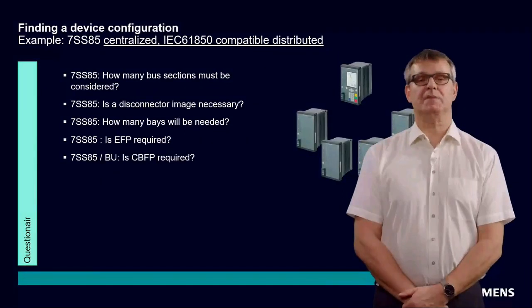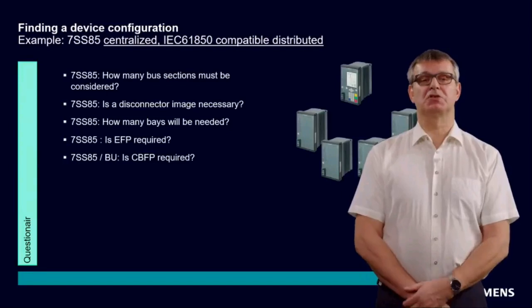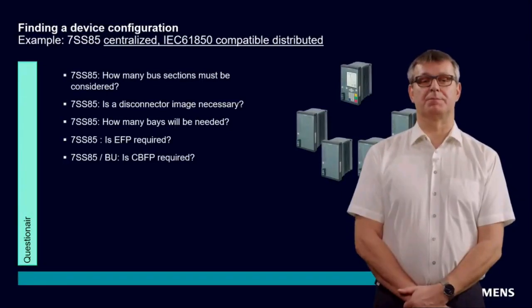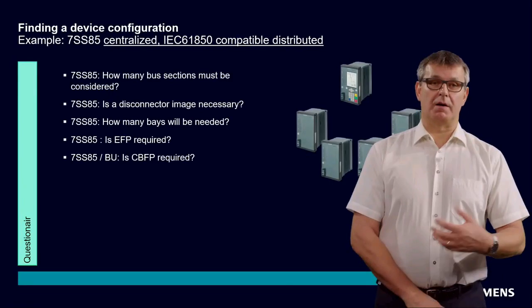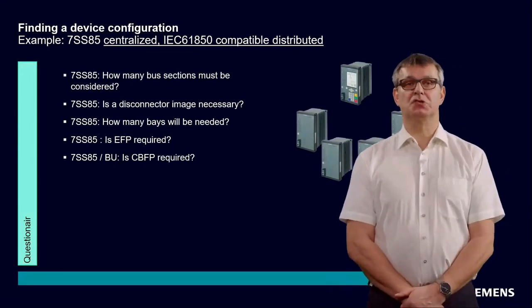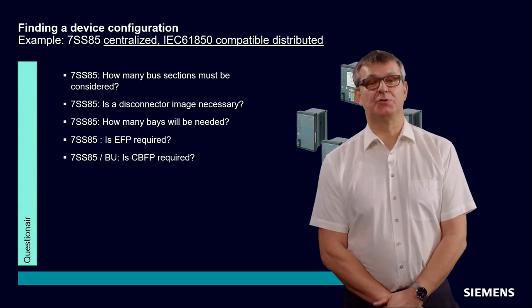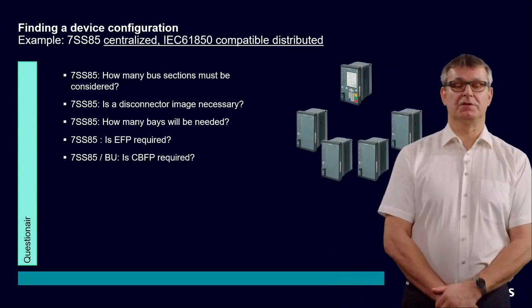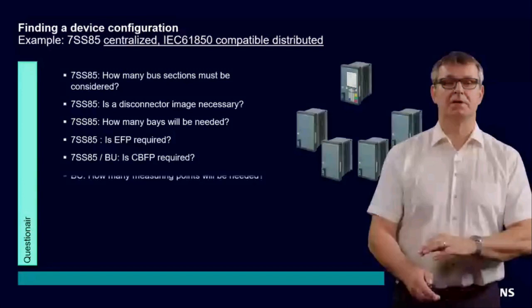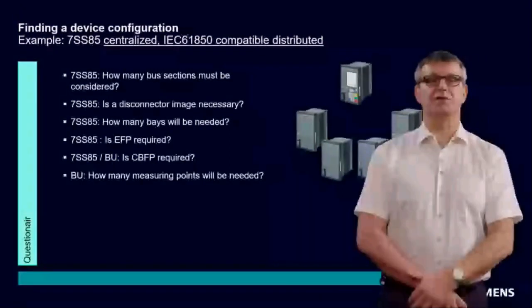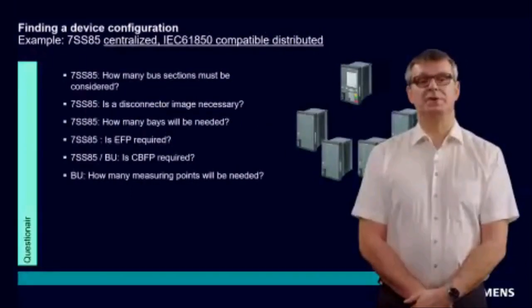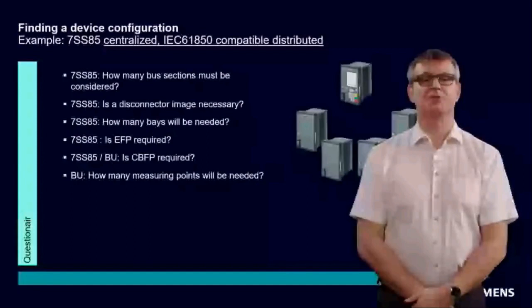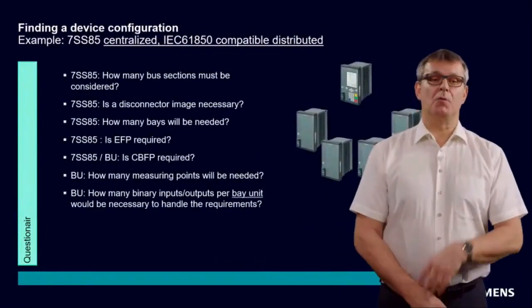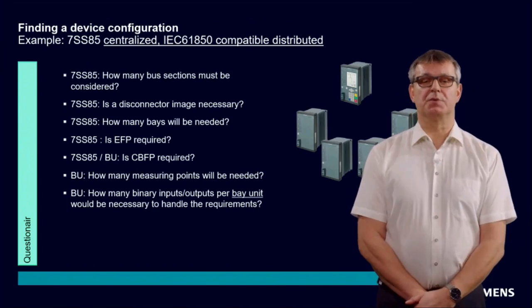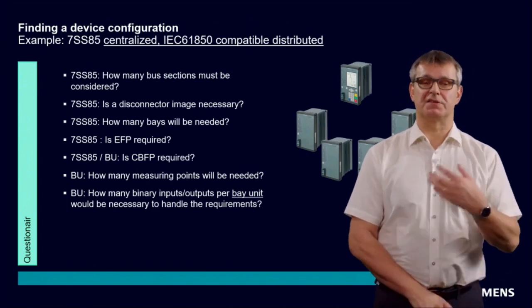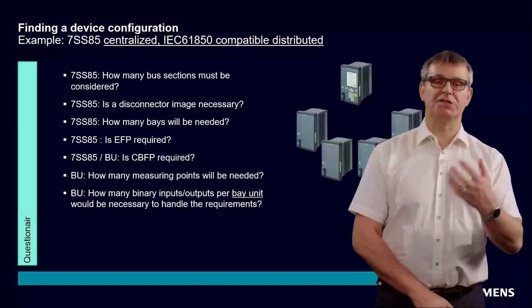The circuit breaker failure protection: do you need a circuit breaker failure protection? Here both approaches are possible. My recommendation is, whenever possible, to use in this solution the circuit breaker failure protection in the bay unit, in the merging unit. And of course, how many measuring points will be needed? This question has to be answered for the bay unit. And how many binary inputs, how many binary outputs? As it is a distributed approach, this must also be answered for the bay units.